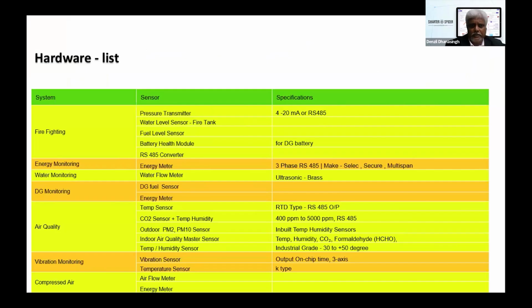This shows some of the data sheets of the hardware list we have. For the firefighting system, you'll have pressure transmitters, water level sensors, fuel level sensors, battery health monitors, and RS485 converters. Energy monitoring uses energy meters. Water monitoring uses water flow meters. DG monitoring uses DG fuel and energy meters. Air quality monitoring covers temperature, CO2, and PM2/PM10 if outdoor. Indoor air quality uses a master sensor with temperature and humidity combinations. Vibration monitoring has a separate vibration sensor. Compressed air monitoring uses airflow and energy meters.